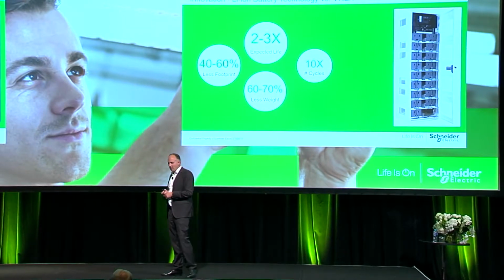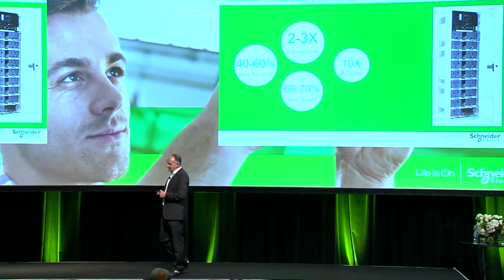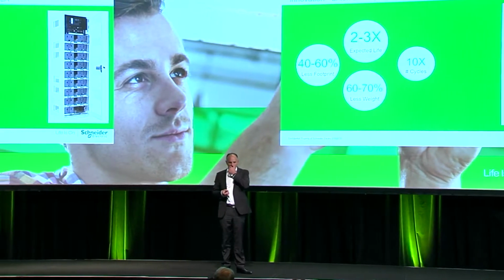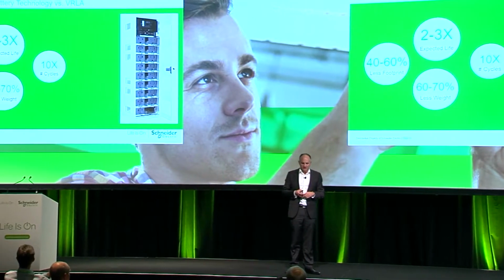So let's have a look at lithium-ion technology now. I believe this is honestly the real next big thing in the data center industry. 40 to 60% less footprint, 2 to 3 times the expected life, 60 to 70% less weight, 10 times the number of cycles when compared with valve-regulated lead-acid technology.